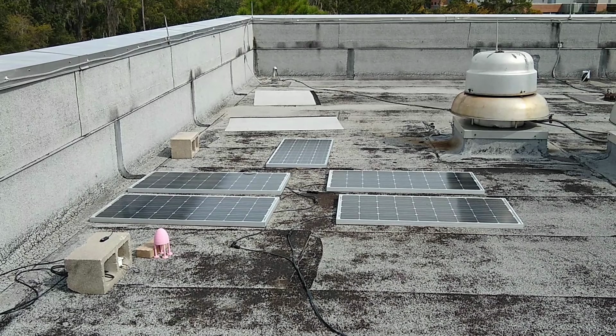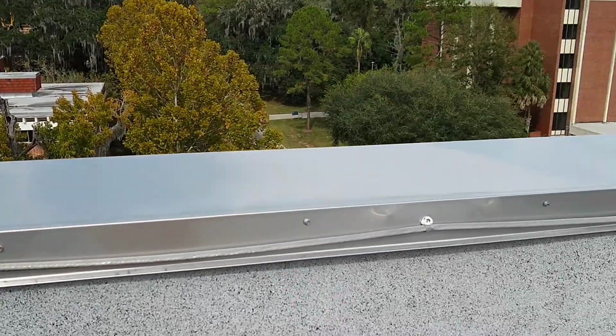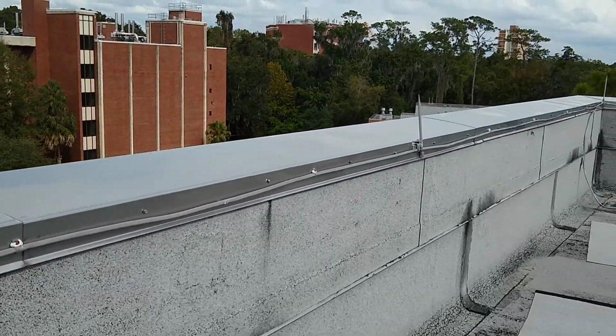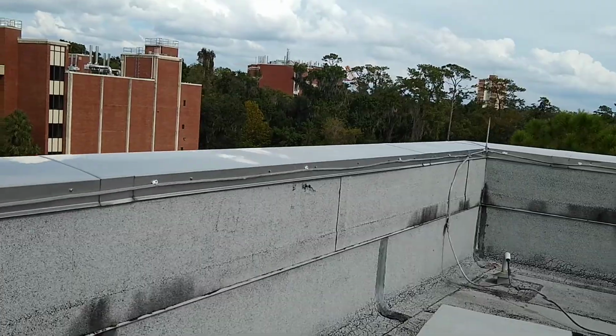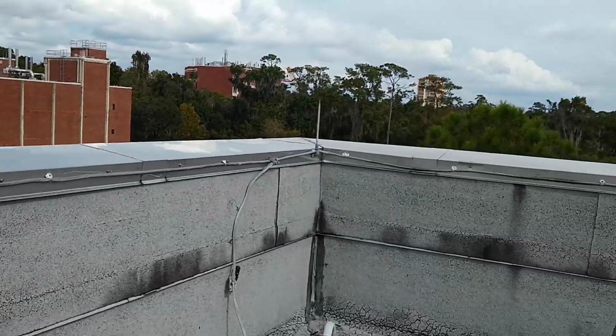In this video, we're going to see experimental results for ground fault and open fault detection using SSTDR in a small string of solar panels. Here we have our 5-panel system next to a ground cable that is a part of the building's lightning protection system. In order to be effective, this system has to be a true ground.